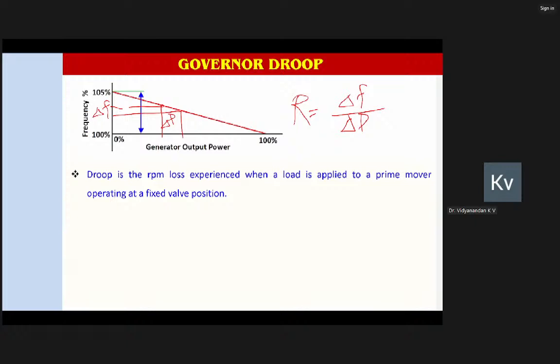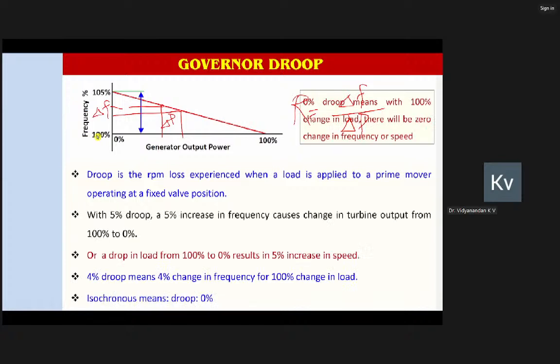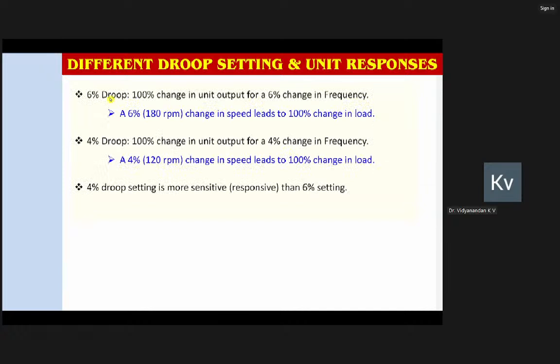Now, for thermal machines, steam turbines, droop is recommended in the range of 2.5 to 8%. But in our country, as per CERC, the droop for thermal machines is recommended in the range of 3 to 6%. And NTPC by default uses 5% droop for steam turbines. That means when there is a 5% increase in speed or frequency, the machine will completely unload. Now, droop actually has an inverse relationship with the machine response. It means if you reduce the droop, the machine will become faster or more responsive. And if you increase the droop, the machine will become sluggish in response.